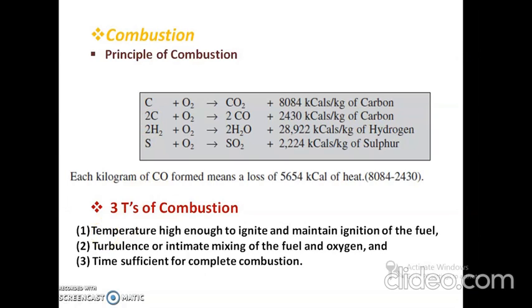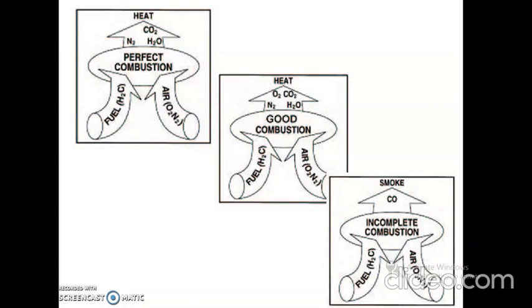So there must be a high enough temperature to ignite the fuel and to maintain the combustion. Then turbulence, or intimate mixing of the fuel and oxygen, is also important, and third, sufficient time for complete combustion. Next, the combustion phenomena is shown, firstly perfect combustion: fuel plus air gives you N2, H2O and CO2, and with good combustion N2, H2O, CO2 and excess O2, which is nothing but the excess air supplied.